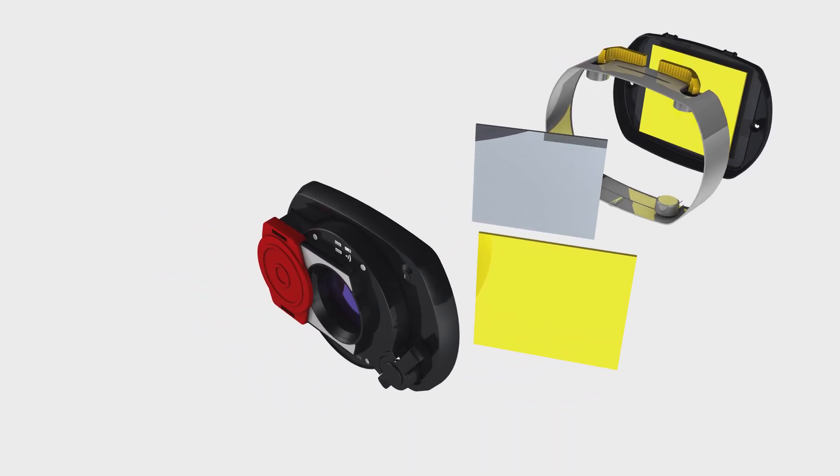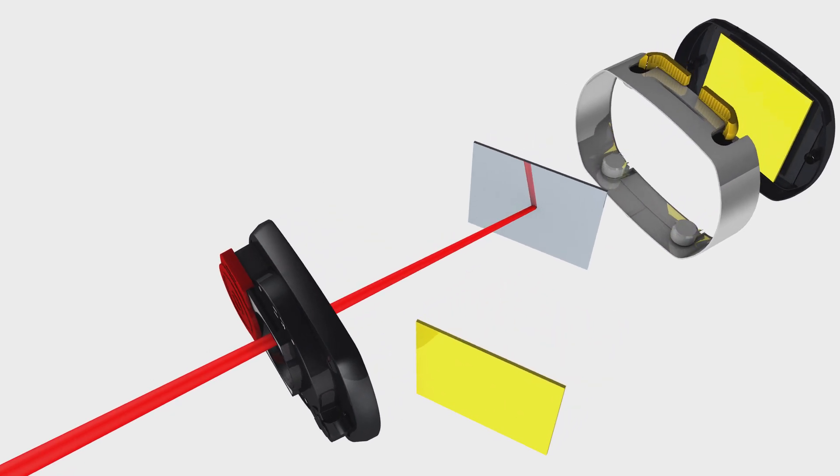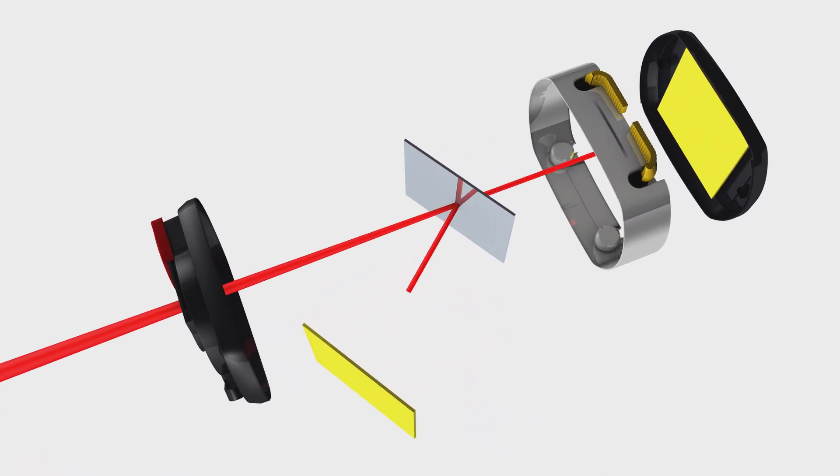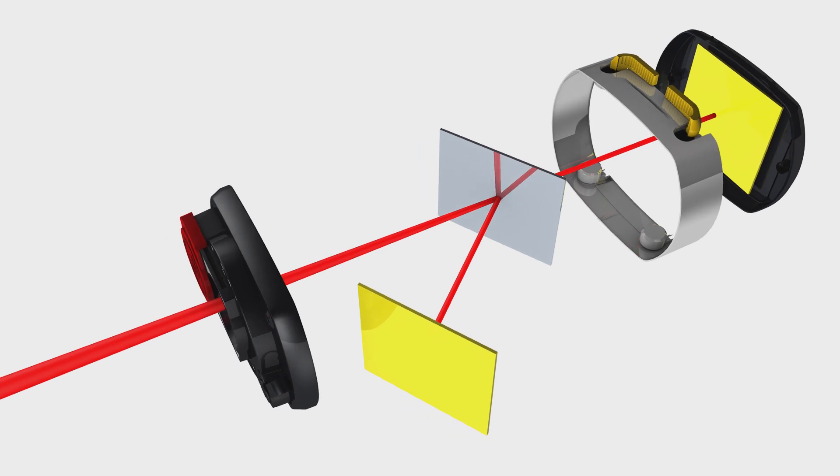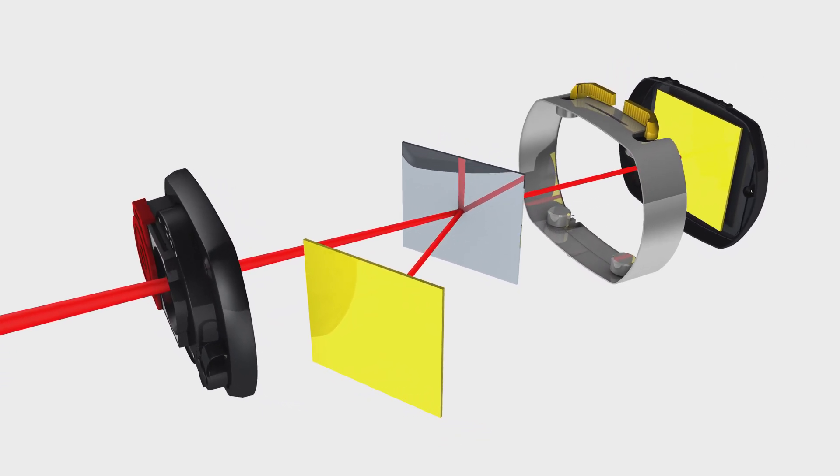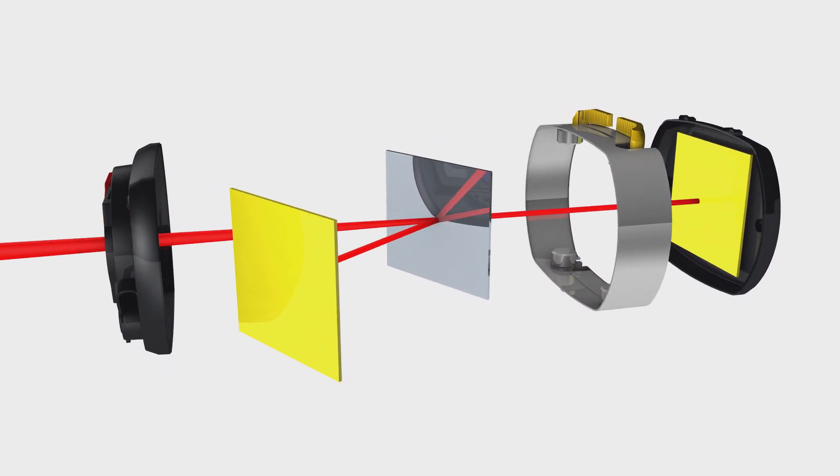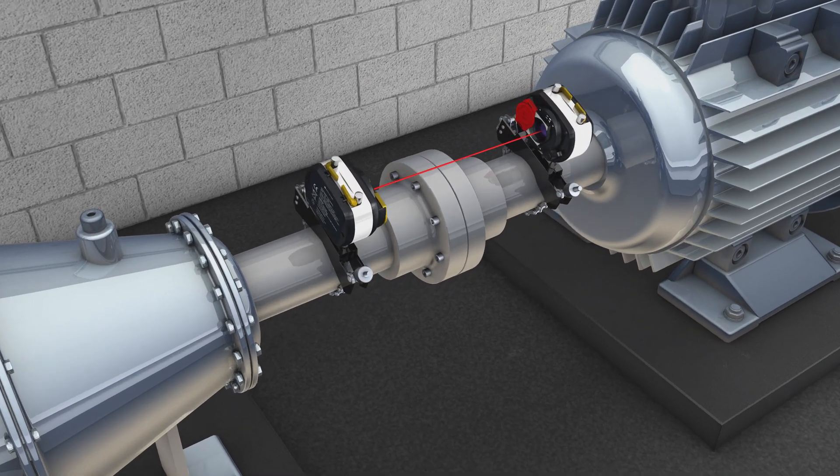A semi-permeable mirror splits the laser beam into two, deflecting one beam onto the front detector and the second onto the rear detector. This worldwide unique technology guarantees that the distance between the first and the second measurement point always stays exactly the same.